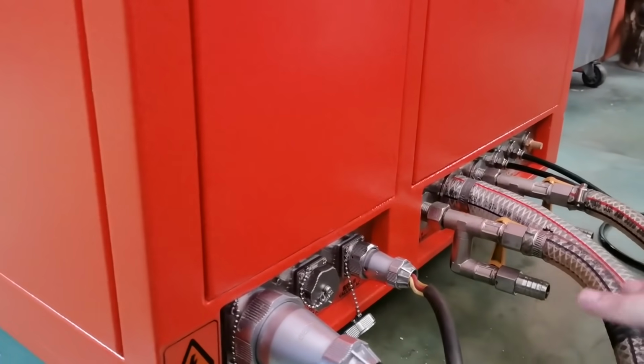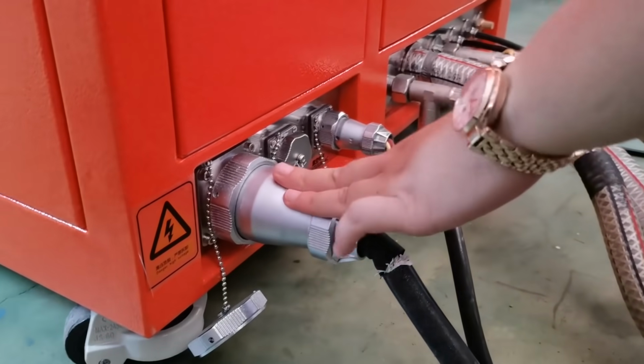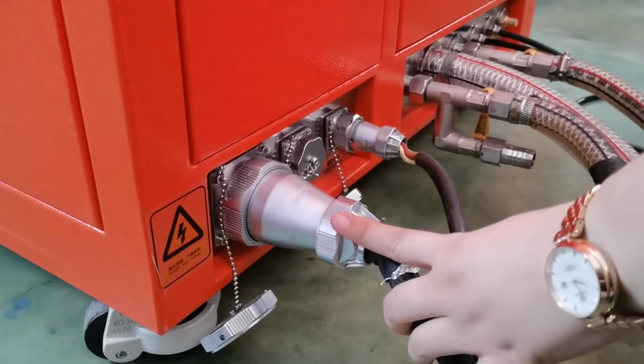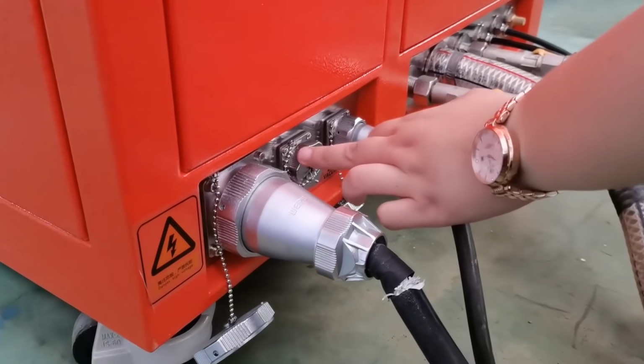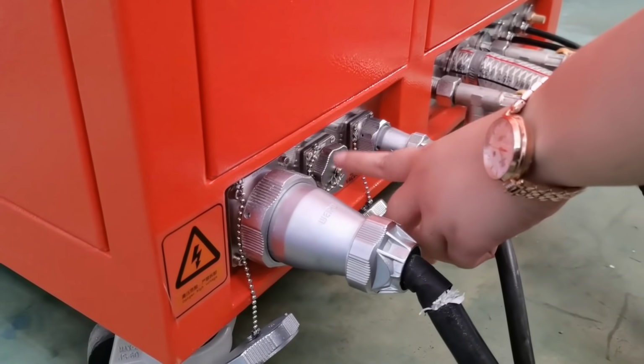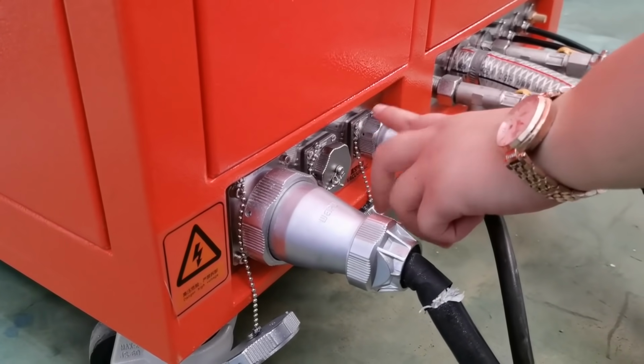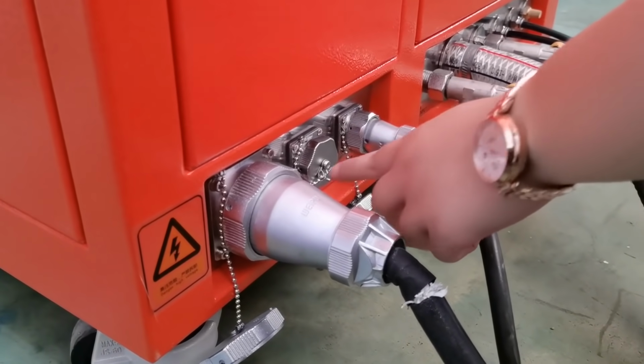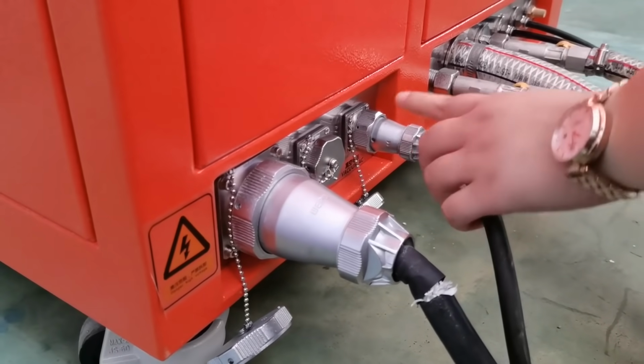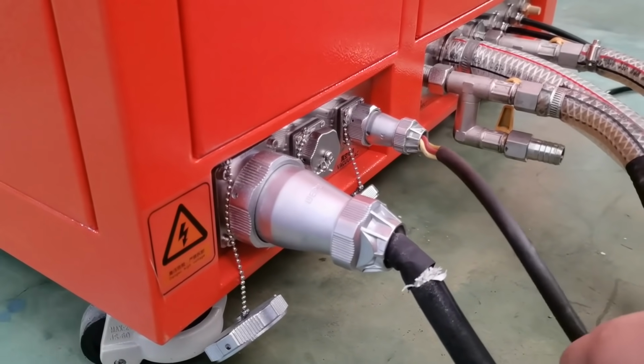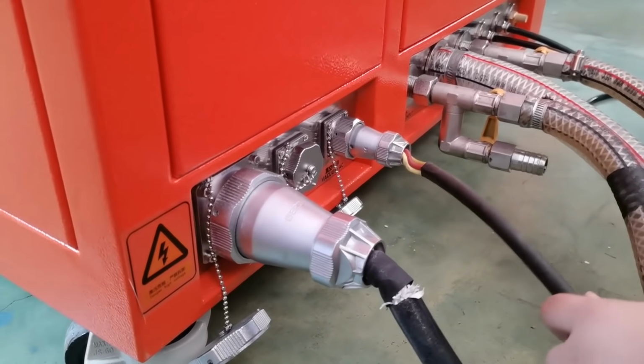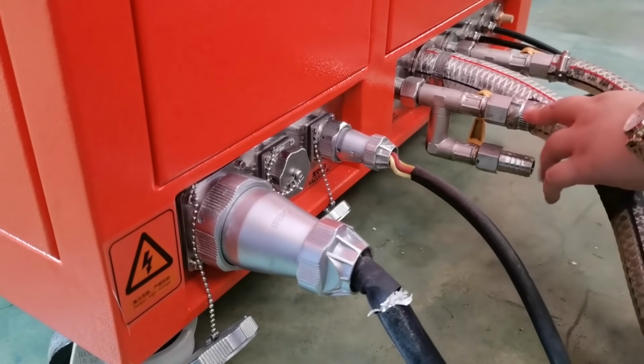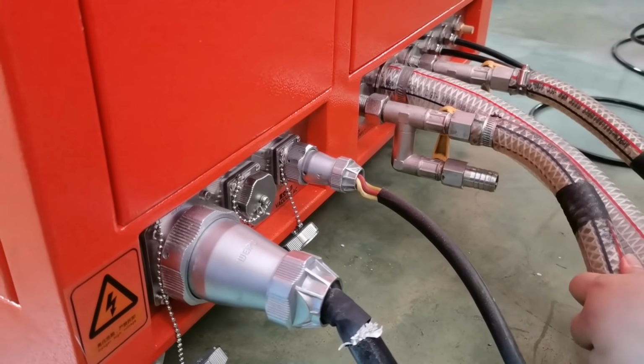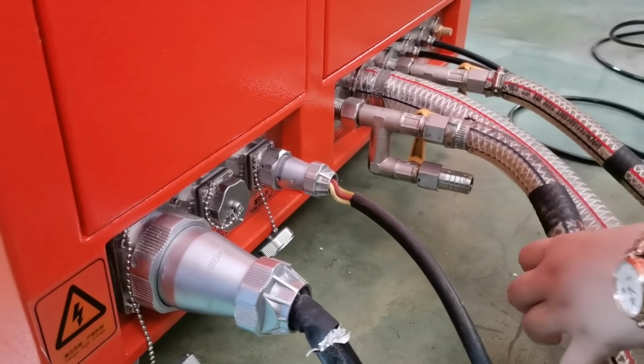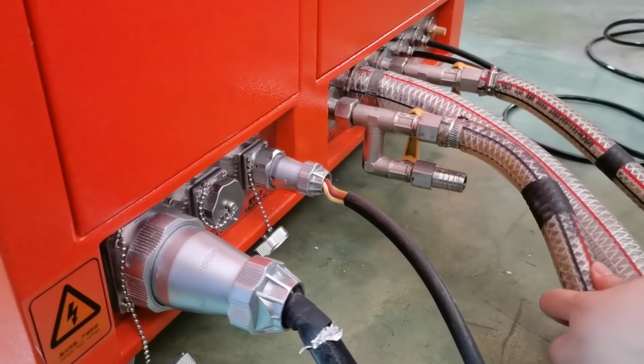Here we can see there are many cables and pipes, and we're going to show you each function. Here is the power cable. This connects to the power supply, and here it connects to the water chiller, because if you use our chiller, the chiller will be controlled by our machine. And here is the connection to the power of the vacuum pump. And here is the water in. This water in means it comes from the water out of the water chiller.